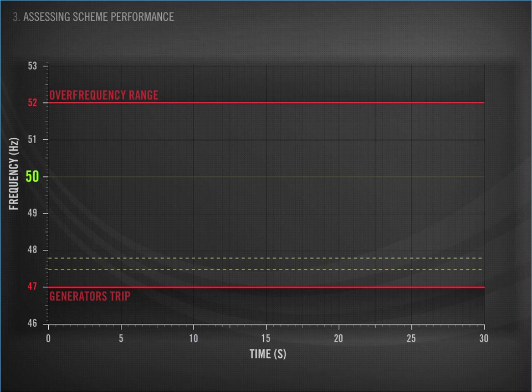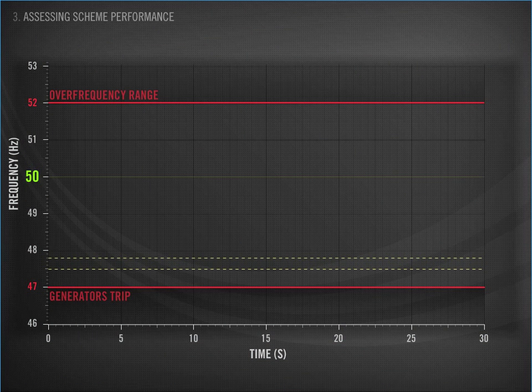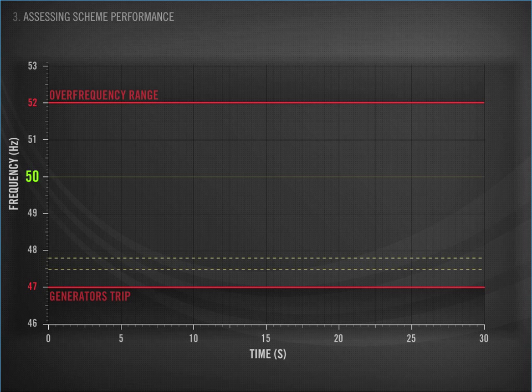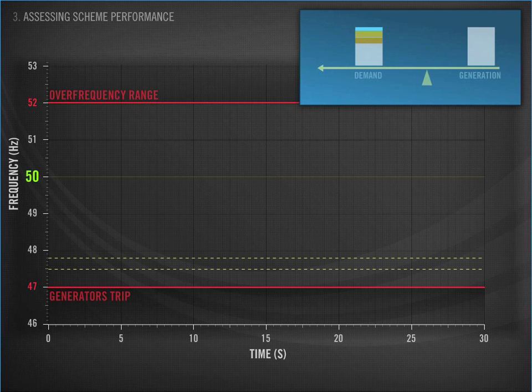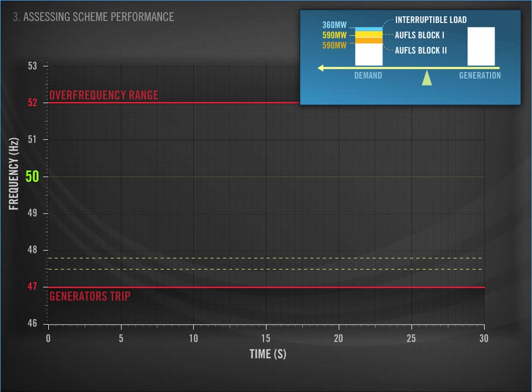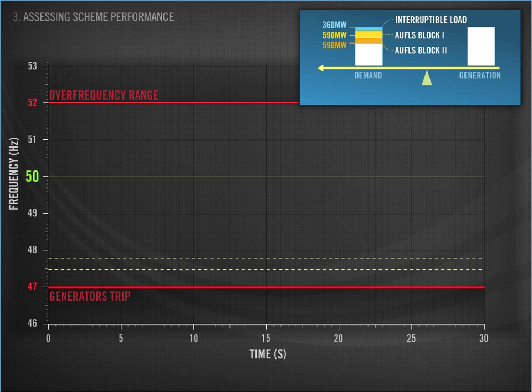Let's return to the graph, which shows frequency on the vertical axis with time on the bottom. Over on the seesaw, we've shown a medium load scenario. You can see interruptible load at 360 MW and two UFLS blocks of 590 MW each. This is the amount of load we can control and disconnect from the grid to tackle any size loss in net injection.